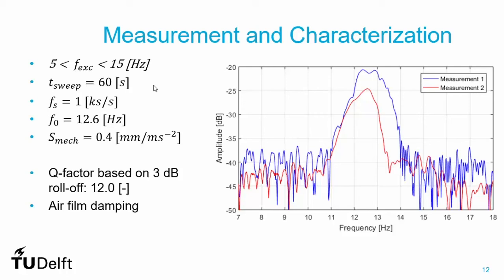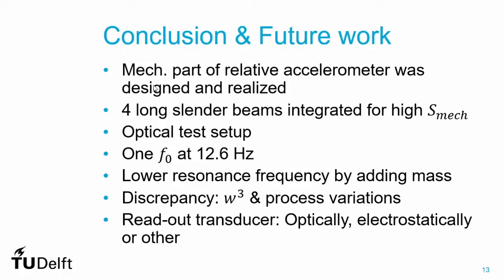In conclusion, the mechanical part of the relative accelerometer was designed and realized. Four long slender beams were integrated in a frame and proof mass to yield maximum mechanical sensitivity. An optical setup was designed for determination of the mechanical spectrum and resonant frequency. A resonant frequency of 12.6 hertz was measured; a lower resonant frequency was obtained by adding mass. The discrepancy from simulation can be explained by process variations and the fact that beam stiffness is proportional to the third power of width. The readout transducer remains an ongoing project for wafer-level integration, either optically or electrostatically.